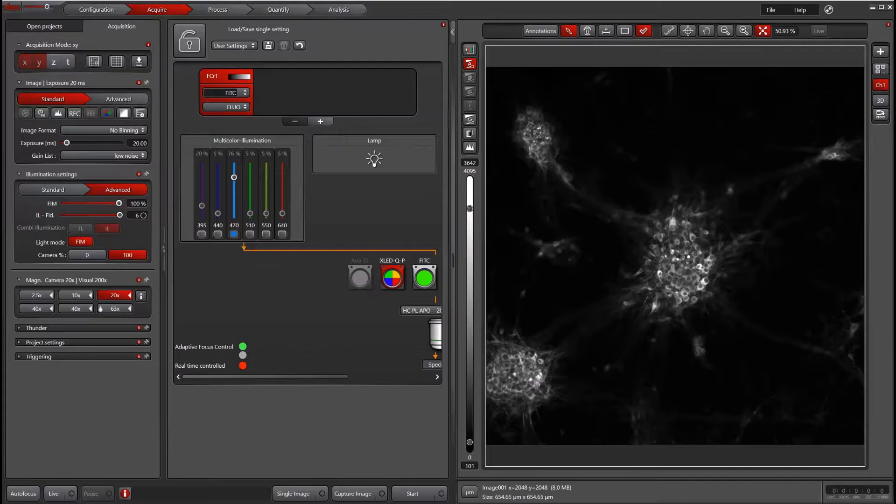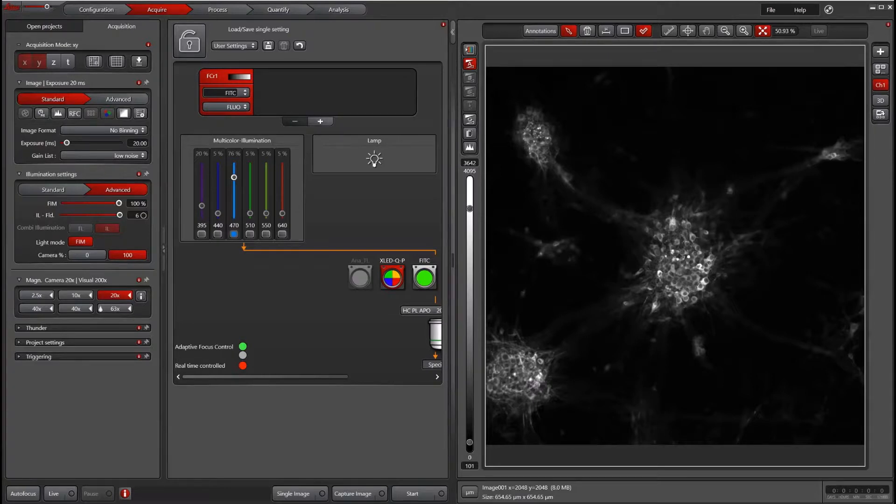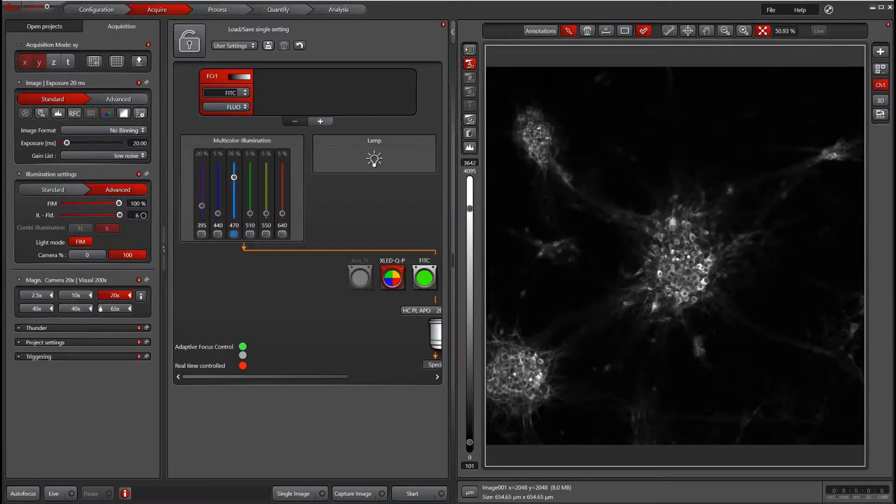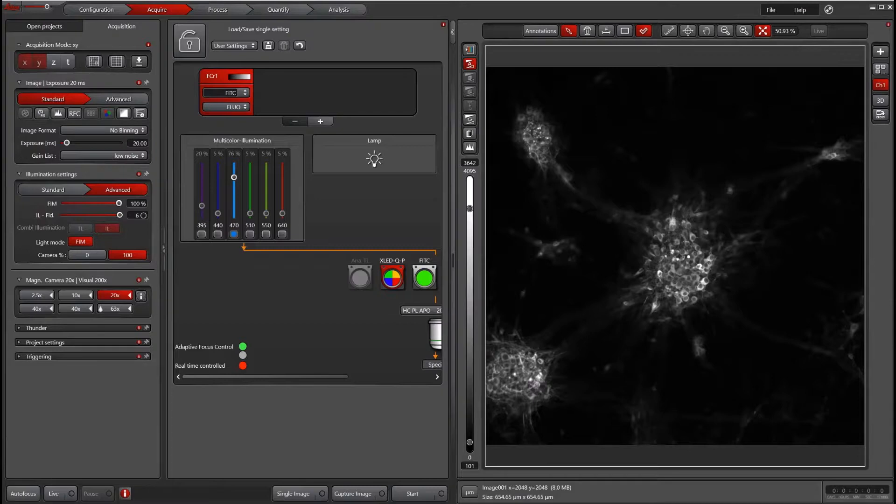Software autofocus works with your motorized Z to run a Z-Stack and identifies the area of best focus. There are two versions of autofocus: best focus and high-speed autofocus. On this system, I only have high-speed autofocus, so that's what I will demonstrate. The good news is that best focus works similarly but is much easier to use.